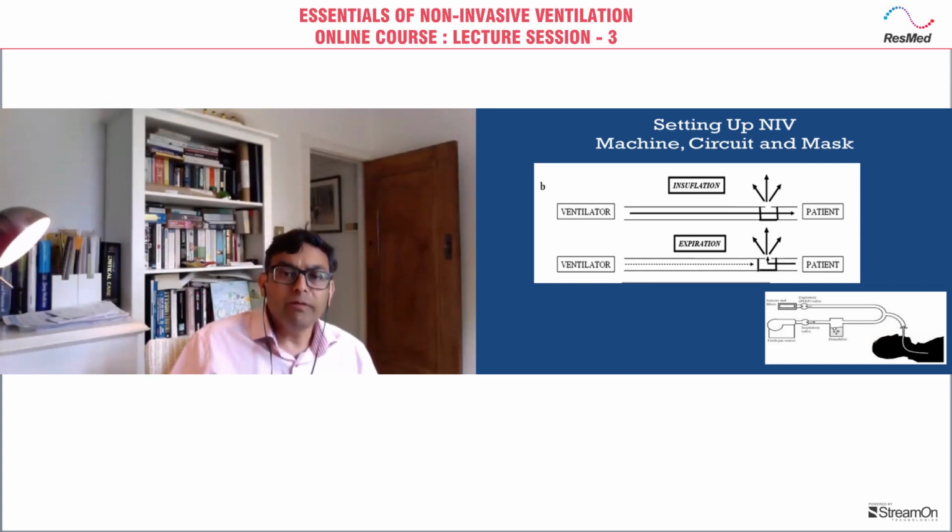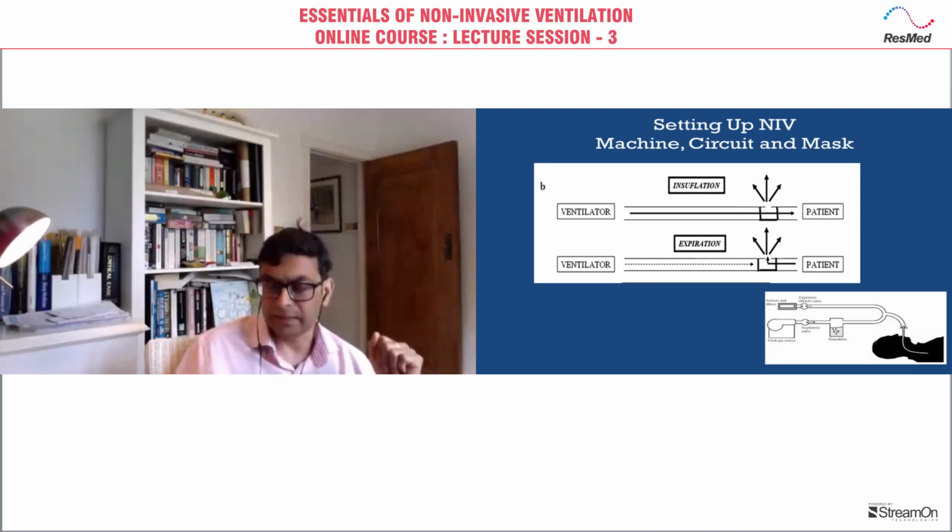Now in non-invasive ventilation circuits, often you have just one limb, and therefore it is really important that we have an exhalation port either in the circuit itself or in the mask. Very, very important. And why? Because it is through this exhalation port that all the gases exhaled by the patient are going to be washed out, so that there is no CO2 buildup in the circuit.